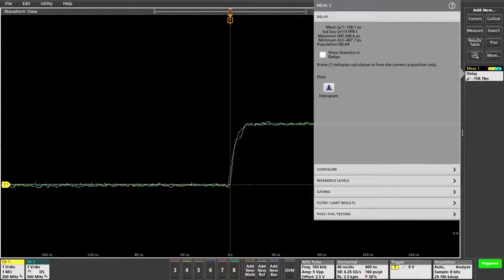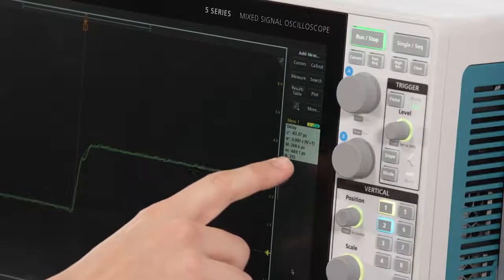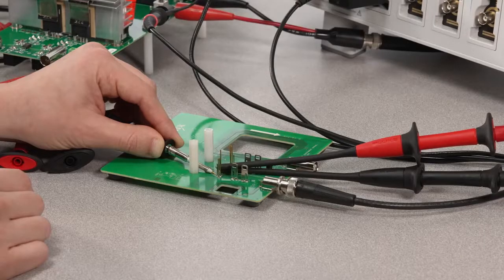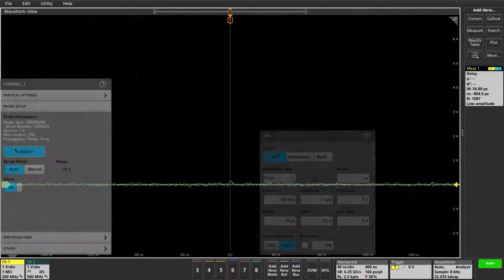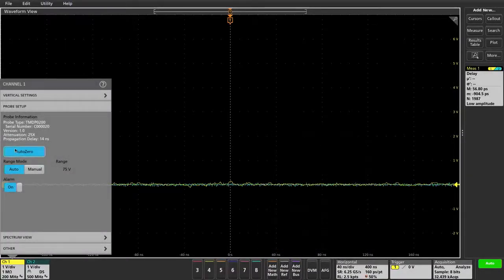If you want to increase deskew accuracy, add a delay measurement. Turn on statistics and collect a few hundred pulses. The resulting average will give a more reliable delay value than a single measurement. Now that the probes are deskewed and warmed up, turn off the AFG and run a quick auto zero. This will remove any imbalance that will affect switching loss measurements.